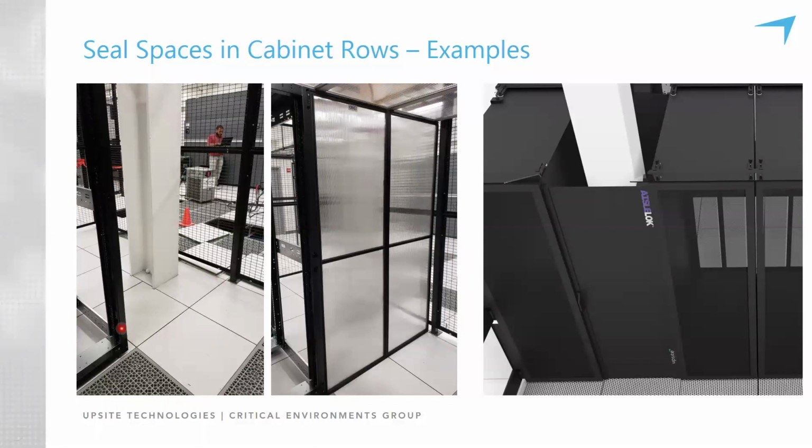So what the customer asked us to do, they required vertical rigid panels, and instead of building one that spans 48 inches wide and the height of the cabinet, there's two of them side by side that are attached to the adjacent panel. And the first one can be removed because this is that roll-in consideration I mentioned earlier, where they would like to in the future be able to roll another cabinet in there, so they can just take the left panel out, put the cabinet in, and reattach the right panel to the end of the cabinet.